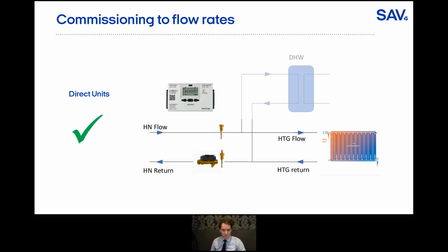Then looking at your radiator circuit side, assuming you're following CP1 guidance and installing the right radiator valves and pressure independent control valves, you can then set up each individual radiator to an exact flow rate. That can all be monitored on that energy meter, and you can commission and verify no matter what time of year, and also it's very much quicker than trying to do temperature balancing and waiting for things to settle. So commissioning to flow rates is the right idea to do.